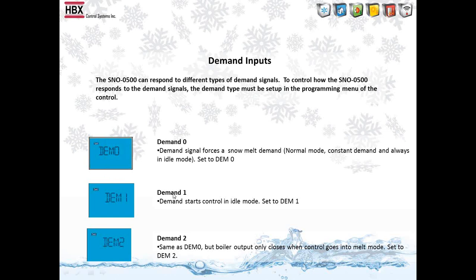And DEM1 is basically that same demand input. If you're in DEM1, it basically turns the control on and allows it to go into idle mode at that point. So you lose the forced melt demand when you're in DEM1 because you're using that as an on-off switch for the control. So that allows the user, if they're away for long periods of time, when they come to that house, they can just flick the switch, turn the control on, so that once they're there, it'll start looking at the optical sensor to see if there's snow, and then it'll go from idle mode into melt mode.